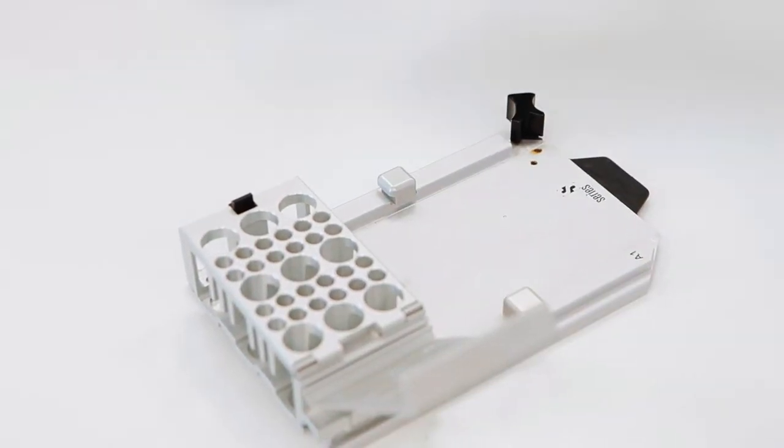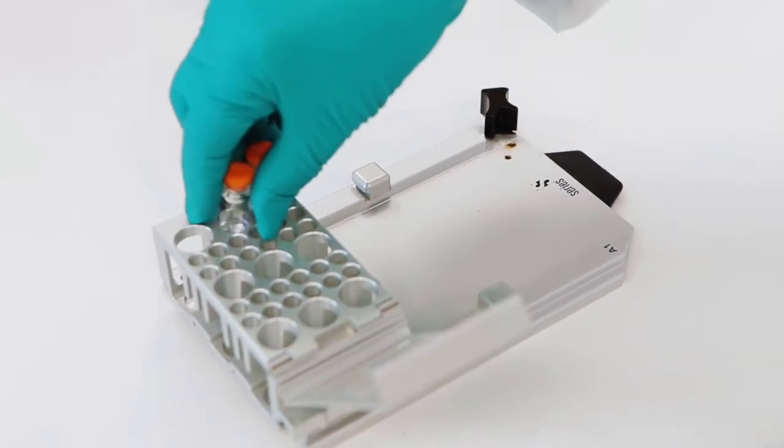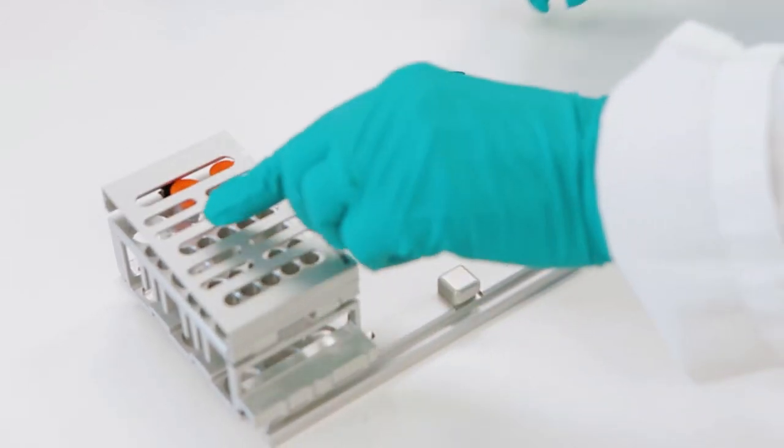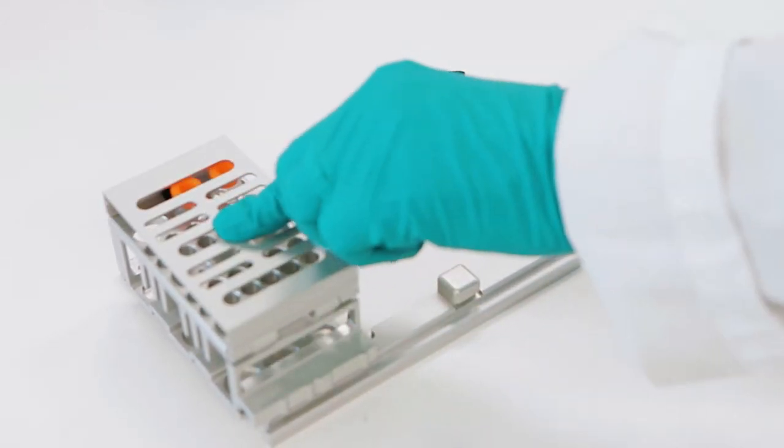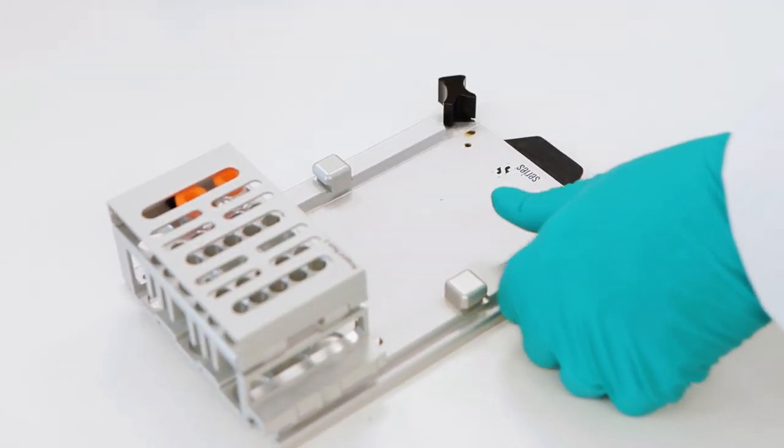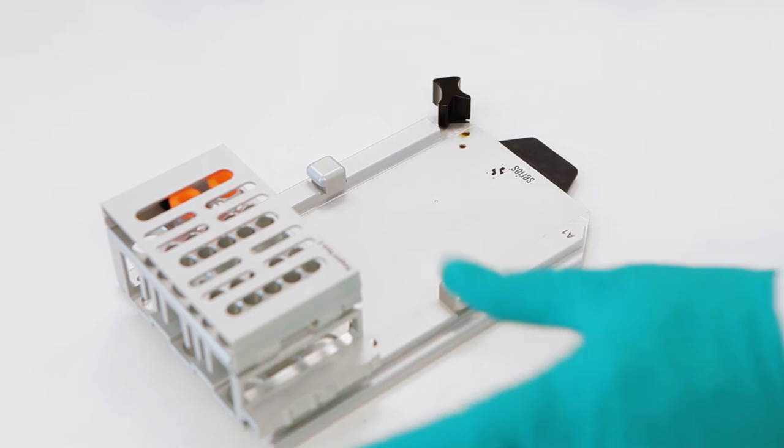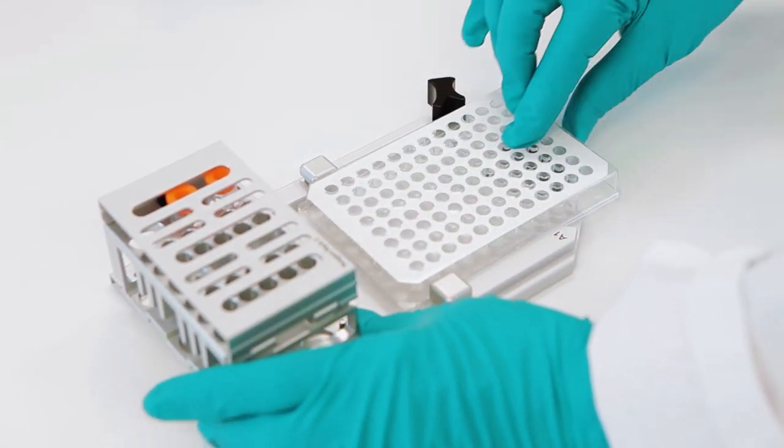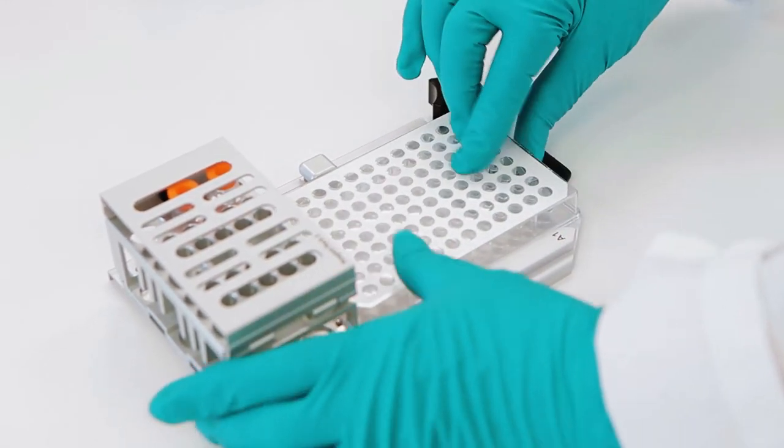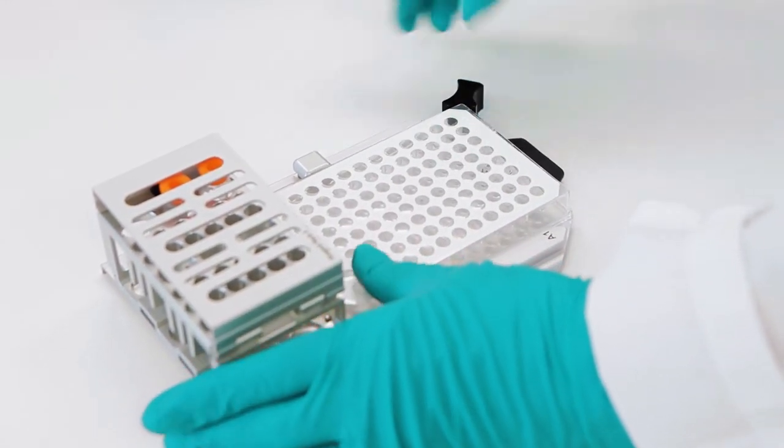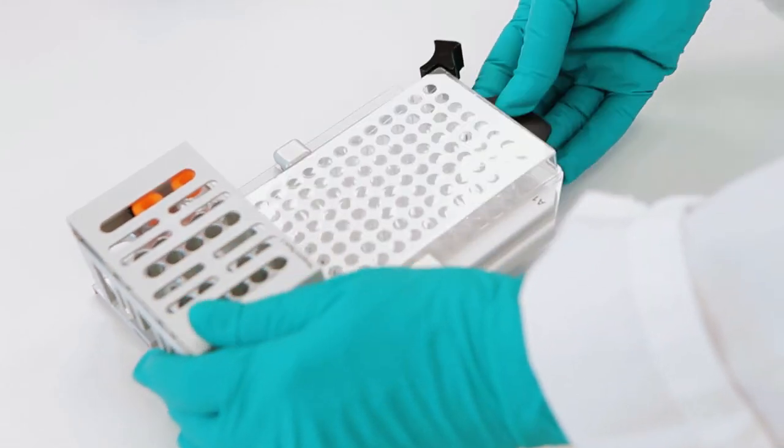Reagents are loaded into the reagent rack like this. To load the plate, pull the lever towards you and to the right, slide in the microtiter plate, return the lever to its original position to hold the plate securely.